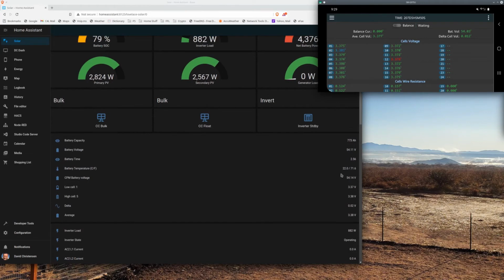I can look at the delta between these two, and they're pretty close. With the calculation I'm doing based on the actual differential to what it's reporting, I've got it pretty close, fairly close to this guy. This one's actually a little bit low, I've seen, comparing to my Klein meters hooked up to the cells. But the data here is very useful to help me determine accuracy, so I get a good idea.